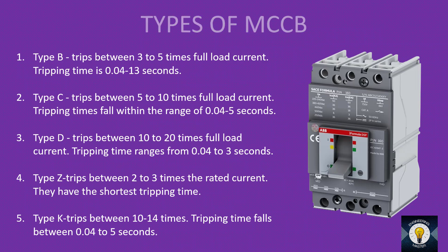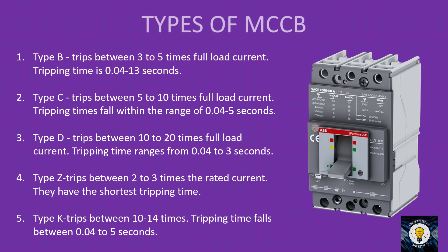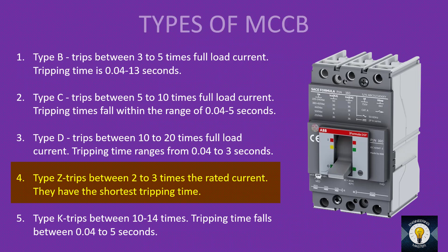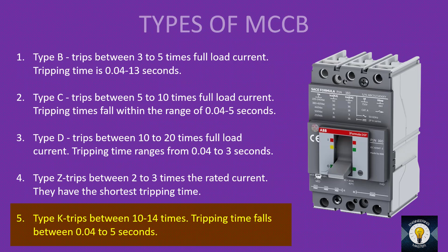The next step is selection of MCCB type. Like MCBs, MCCB is also available in five types. Type B trips between 3 to 5 times full load current with a tripping time of 0.04 to 13 seconds. Type C trips between 5 to 10 times full load current with a tripping time of 0.04 to 5 seconds. Type D trips between 10 to 20 times full load current with a tripping time of 0.04 to 3 seconds. Type Z trips between 2 to 3 times full load current and has the shortest tripping time. Type K trips between 10 to 14 times full load current with a tripping time of 0.04 to 5 seconds.